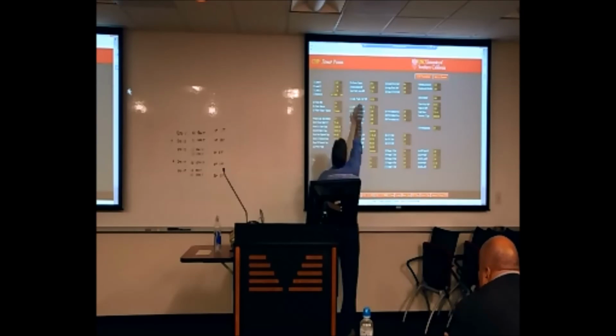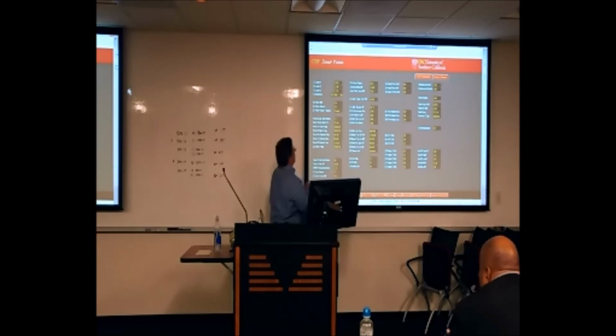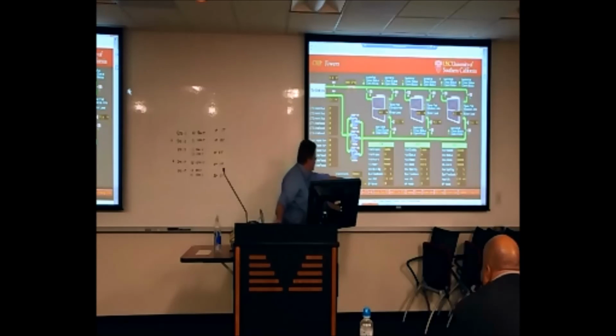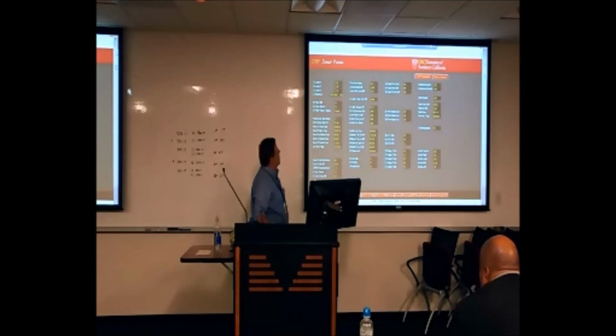Here's our wet bulb limit set point based on the wet bulb outside, our wet bulb plus 3. Right now it's saying it wants plus 7, so it wants to be 70 degrees, which should tell us the wet bulb was about 63. We'll back that up and see. Back to graphic. And our outside air wet bulb is 63. 63 plus 7 is going to be 70, and that's where it's wanting to cap that speed, if it were in that automatic mode. Right now we're in the fixed condenser water supply temperature set point mode, but if it were automatic, it would be capped at 70 and not let it go below 70 based on the outside air wet bulb limit.